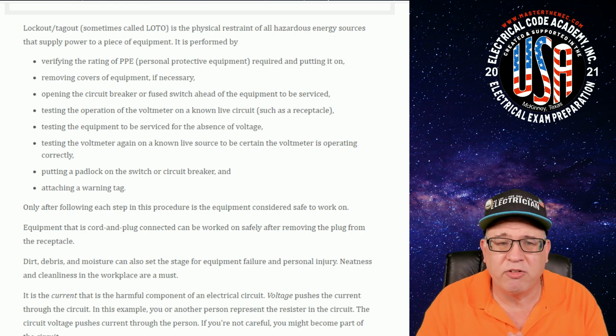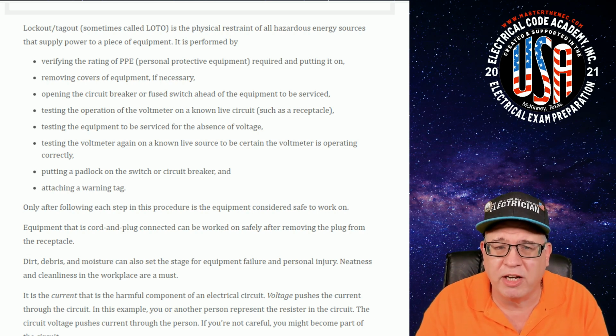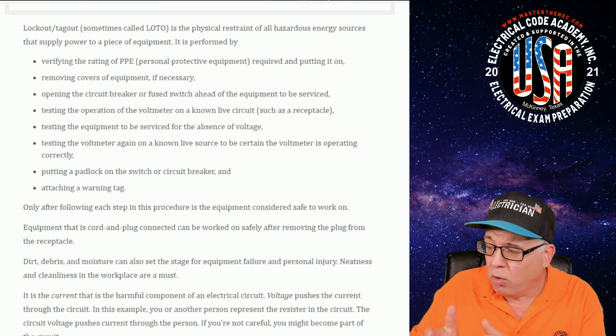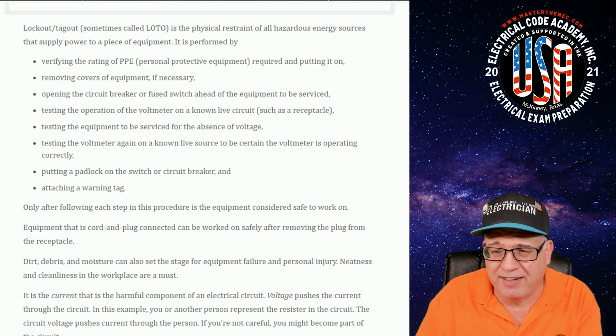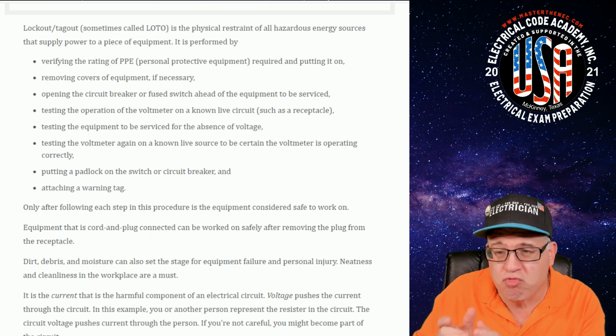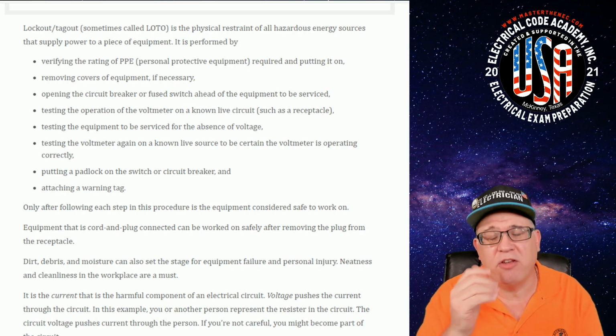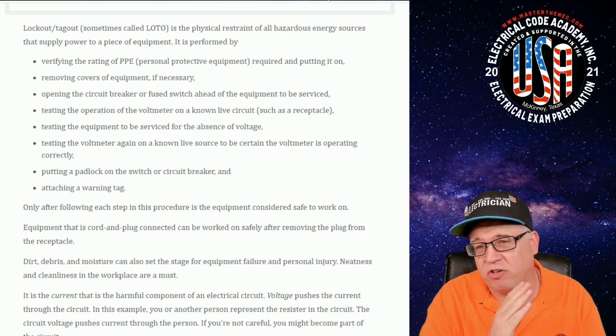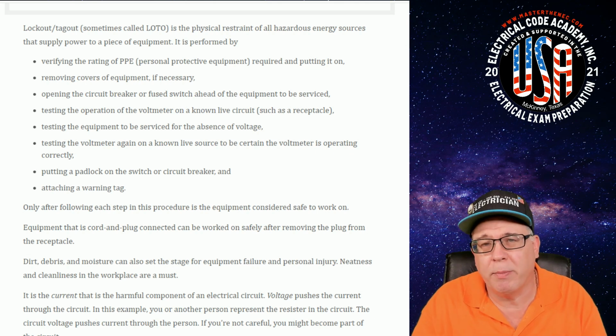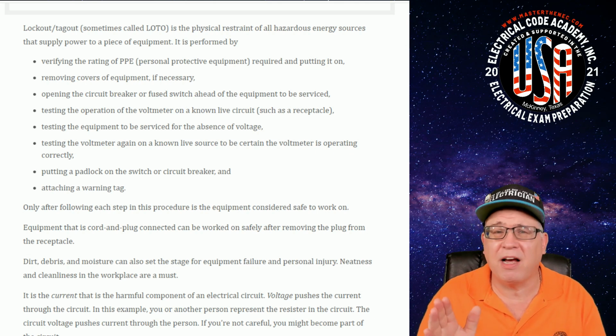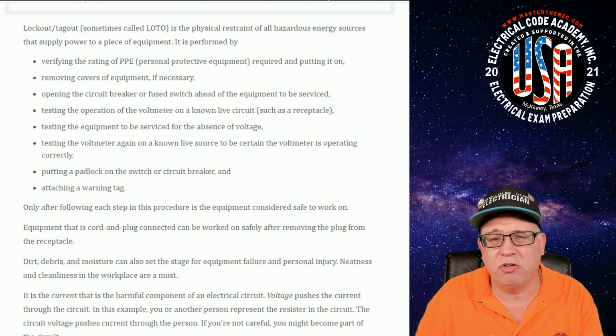Next, test the operation of your voltmeter on a known live source. Make sure your equipment works properly, test it, verify it's working on something you know is working, and then use that to confirm you've successfully de-energized the equipment you're going to work on. Sounds like common sense, but how often do you actually do that?